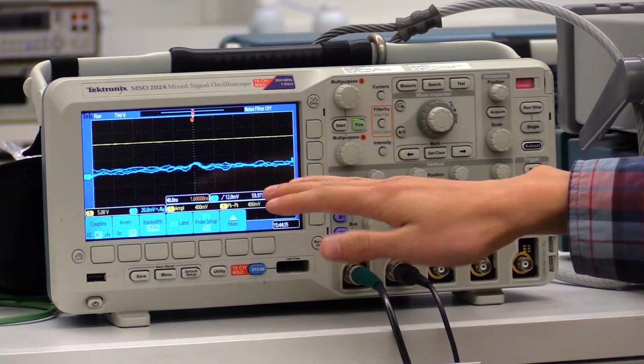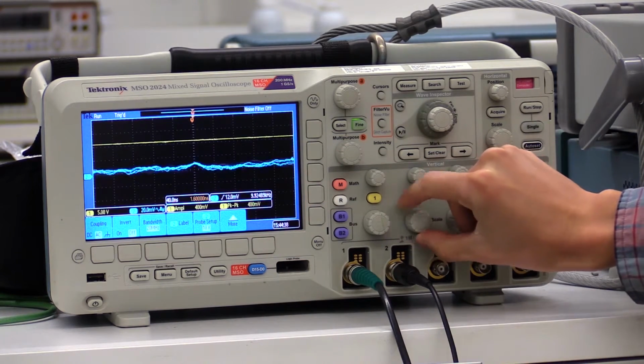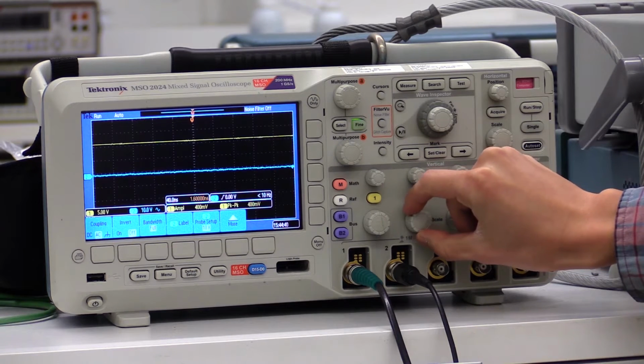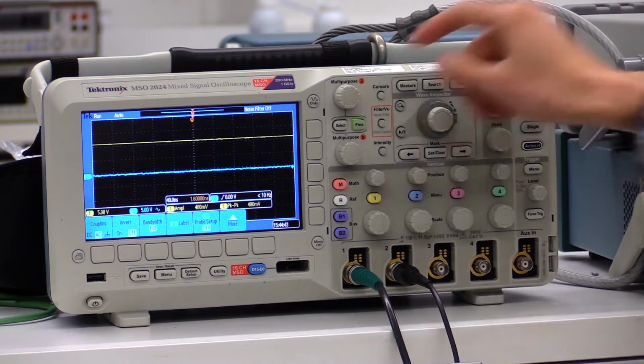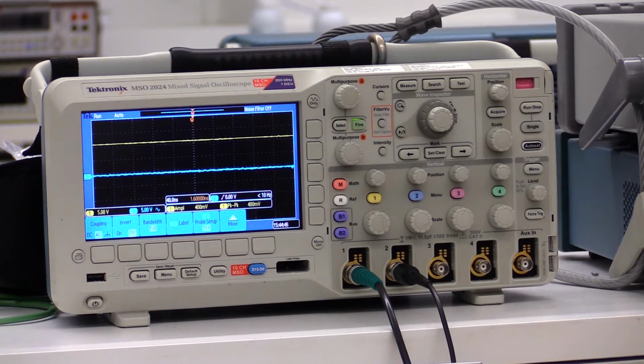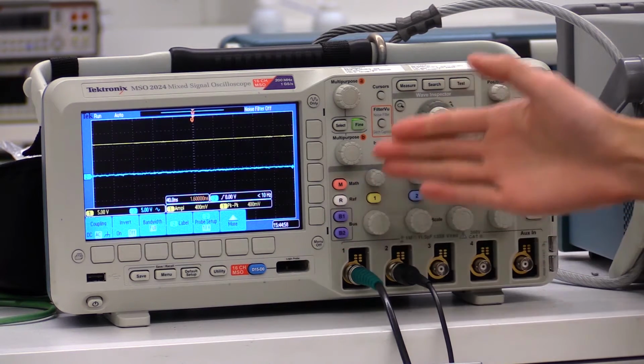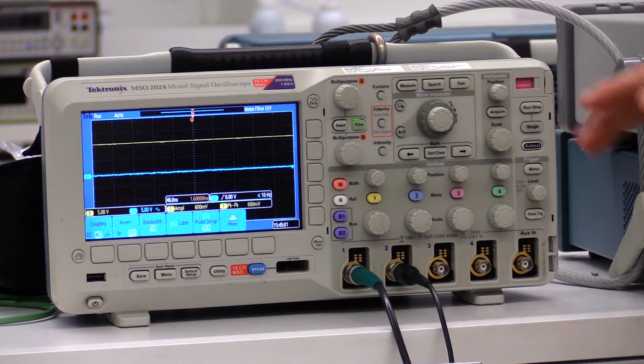So for this purpose, we're going to match the divisions. So I'm going to bring this up to 5 volts as well. And this is at 0, and since it's not connected to anything, we expect it to be 0. So what the probe does is it can take a high voltage signal and properly display it on the oscilloscope, whereas, as we saw before, if each division is only 5 volts, there's going to be a max ceiling for what the mini grabbers can measure. So the probe has the option to go to times 10 measurements, which means it'll take whatever actual voltage you're measuring, and then it'll divide it by 10.